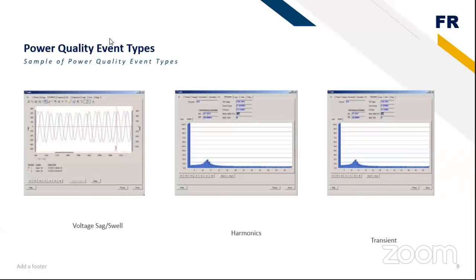If we can determine, hey, you have a neighbor up the line from you who seems to be starting large motors at various points in time, and it's causing a disruption to your facility, which causes relays to drop out, which causes some motors or starters to go below their threshold, why is that equipment shutting down and then having to restart?